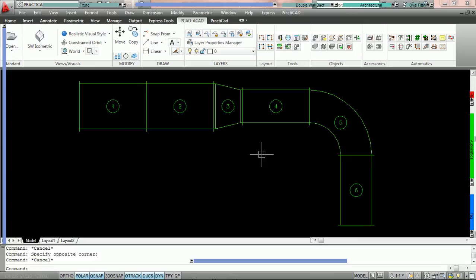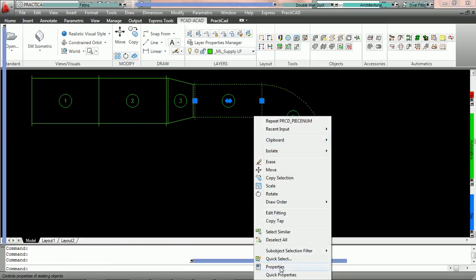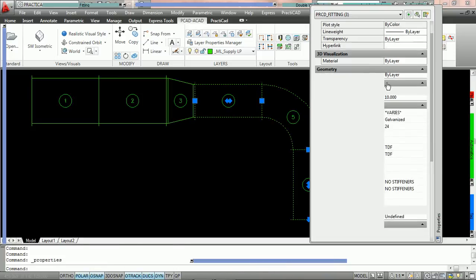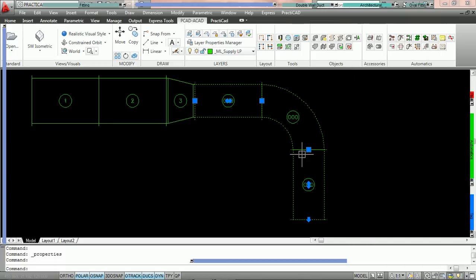The last thing we need to show you is how you would renumber the duct if you wanted to and you still had that condition active. If you wanted to renumber duct, you'd have to use some sort of selection automatic. Here we're just going to hand pick the ducts that you would like to renumber. Go to the AutoCAD property box and make sure that in the field for piece number, for the ducts you'd like to renumber, it doesn't have anything in it. What we're going to do here is click on piece number, hit the delete key on the keyboard and hit enter. That's going to bring the tags back to undefined. And undefined means 0. The particular custom tags I used here do show 0 when there is no number for the duct.